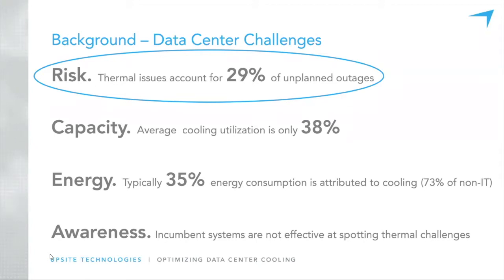I realize this is a very well-known stat, and there are hundreds of this type of stat banded about in the industry, but typically 35% of total mains incoming in a data center facility is used on cooling, which accounts to about 73% of the non-IT load.